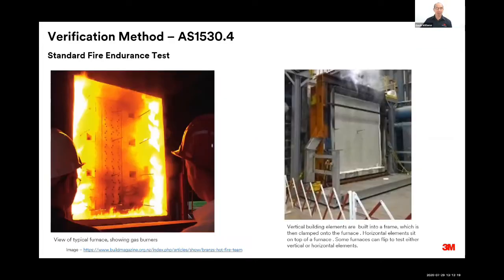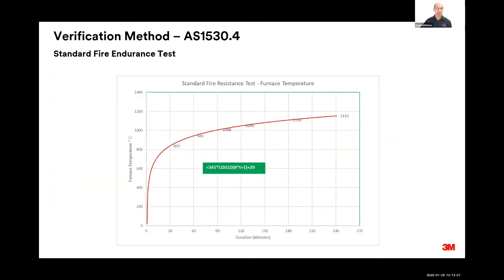Here's some pictures showing the apparatus for the standard fire endurance test. In this case, it's AS 1530.4, a picture of that, and you can see there that there is a furnace through to which a test specimen, which could be a wall or a floor, or it could be a door, a fire-rated door, and it could be a wall element that's penetrated with items such as pipes and ductwork. That element is bolted onto that furnace and subjected to that fire endurance test. And you see here, I've got a graph showing the temperatures that element is exposed to. And after 2 hours, we're up to over 1,000 degrees of temperature and radiant heat. So quite onerous.